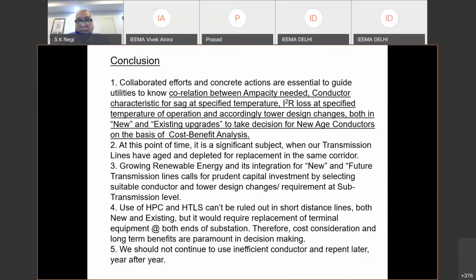A correlation between ampacity needed: conductor characteristics of sag tension at specified temperature, I-square losses at specified temperature of operation. Accordingly, tower design changes, new and existing upgrades, to take a decision on a new conductor on the basis of cost benefit analysis. So I have put here a very important factor: I-square loss, tower design changes.